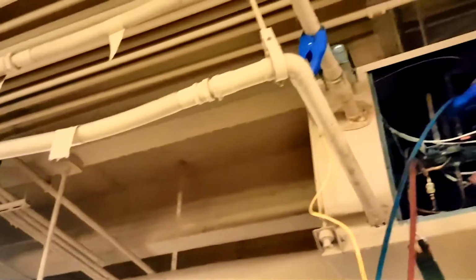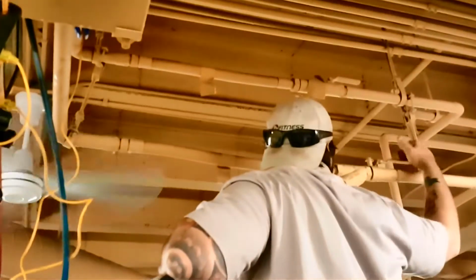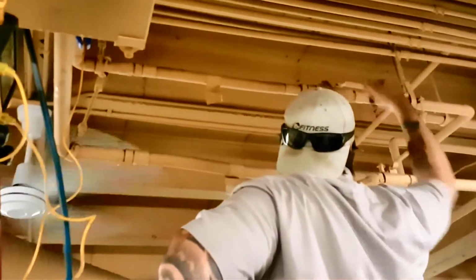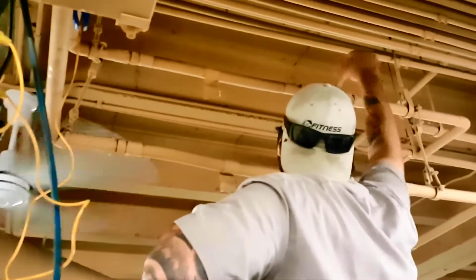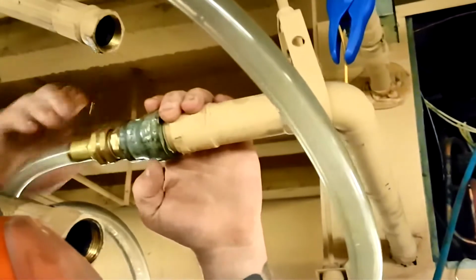We're going to be disconnecting the hoses out of the unit. Right now the unit's running, so we're going to turn the unit off, disconnect the hoses so we can tap into the system. Alright, so Jonathan's going to be shutting off the valves at this point to make sure that you have no water flow coming from the cooling tower. And then he's going to be disconnecting the lines.